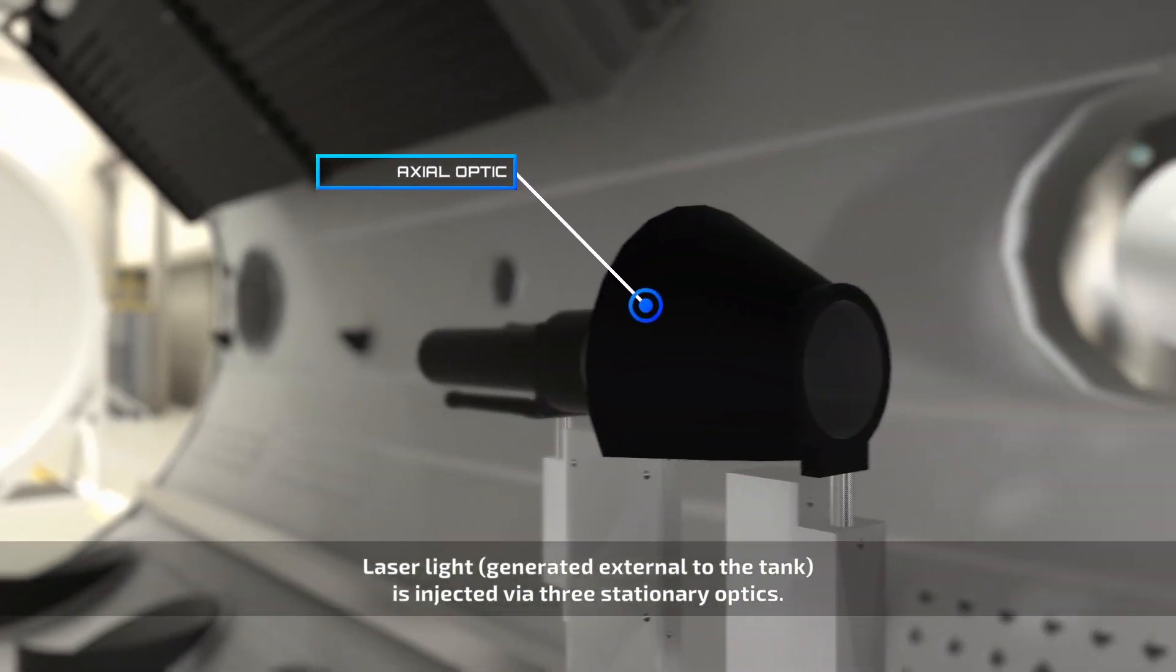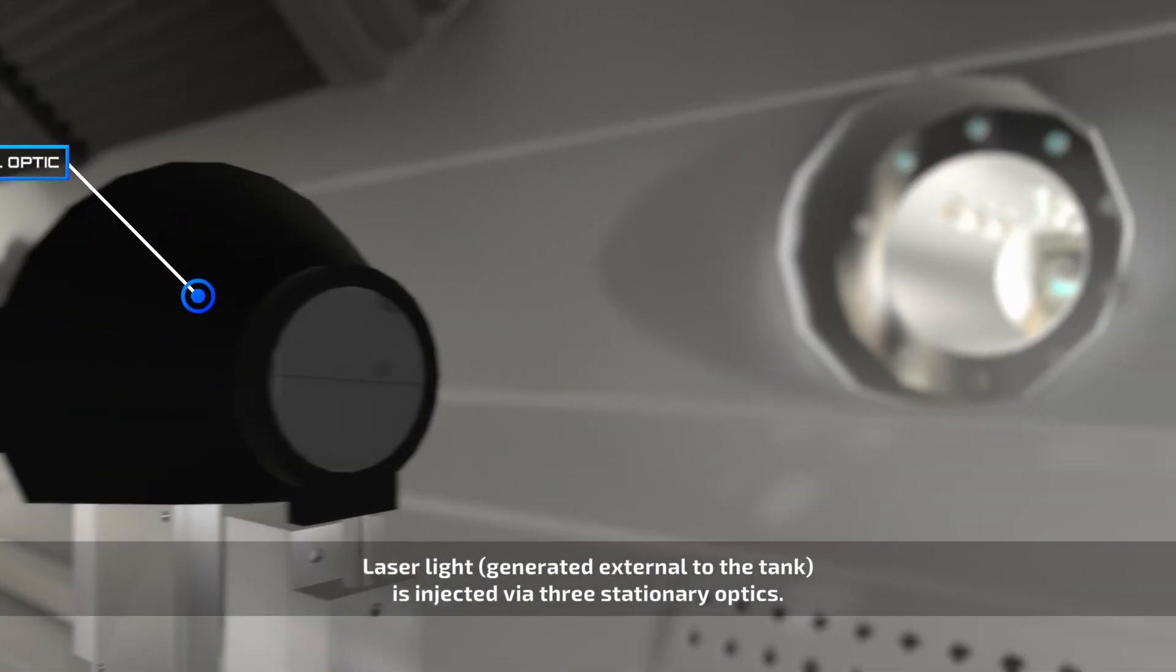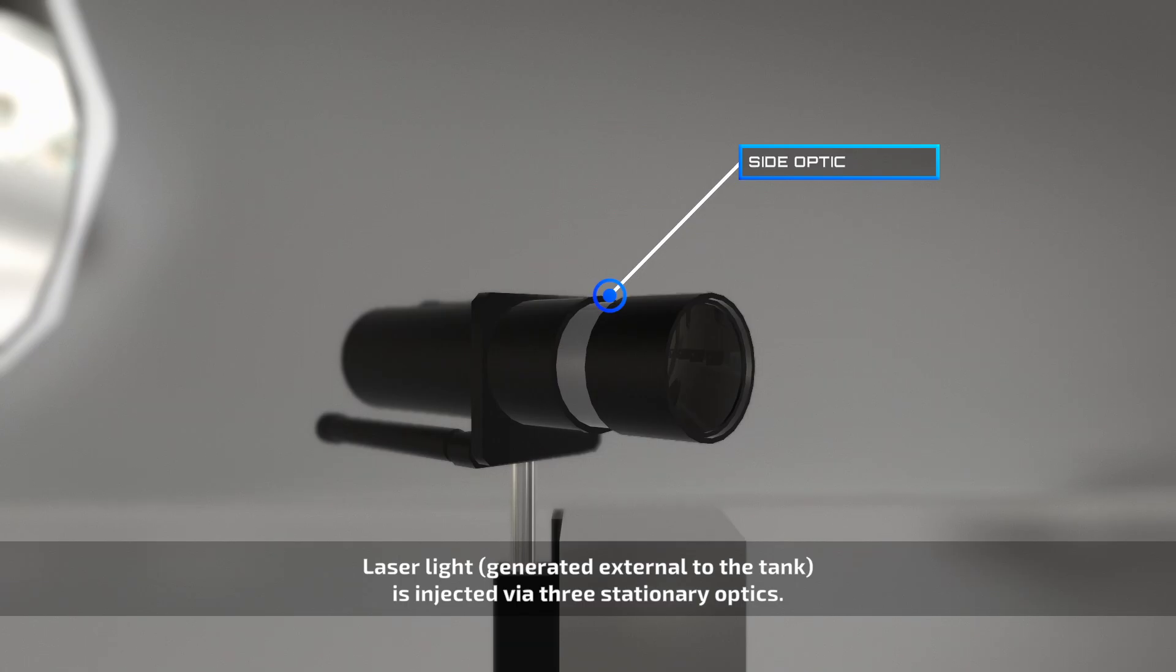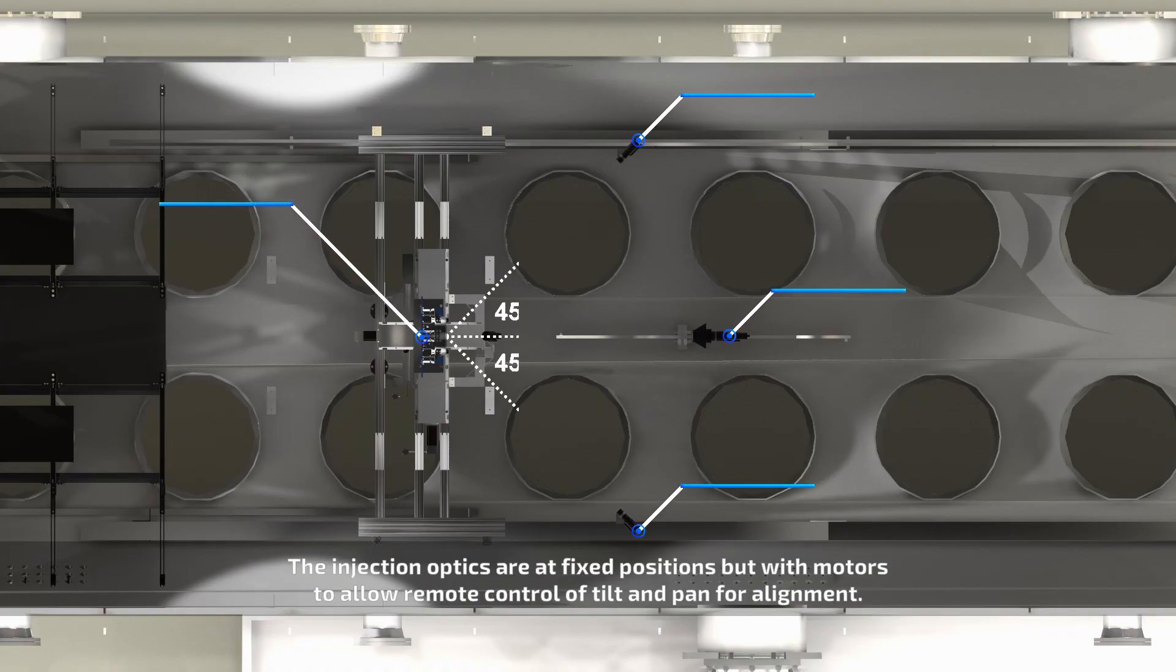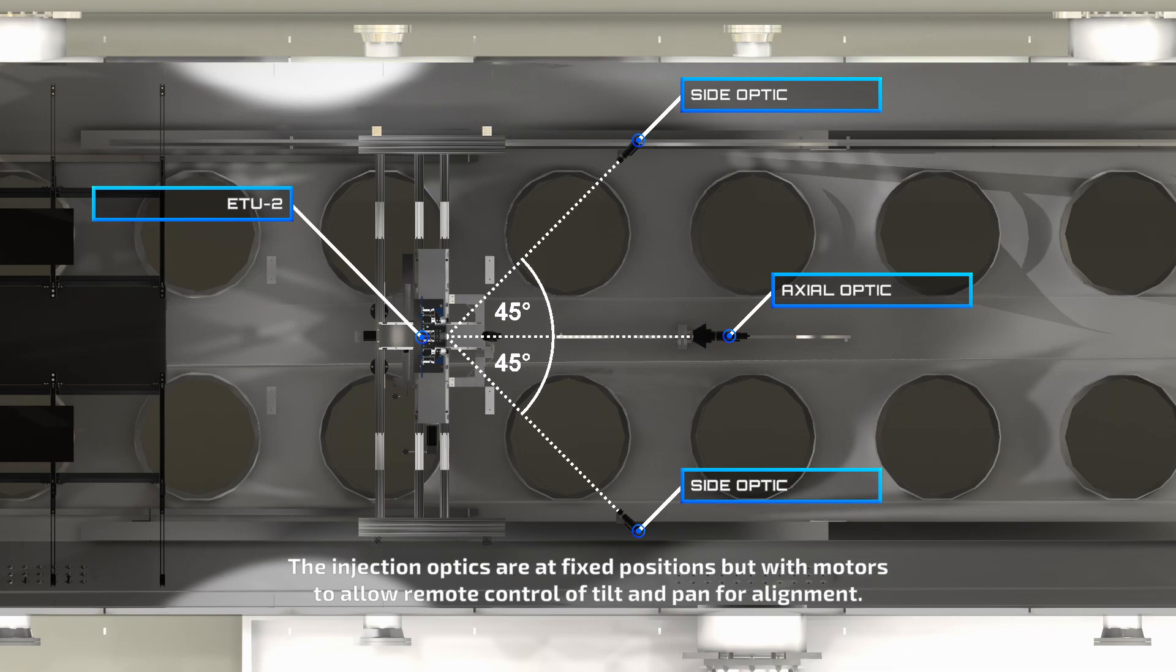Laser light, generated external to the tank, is injected via three stationary optics. The injection optics are at fixed positions, but with motors to allow remote control of tilt and pan for alignment.